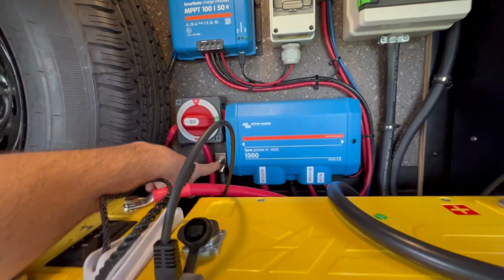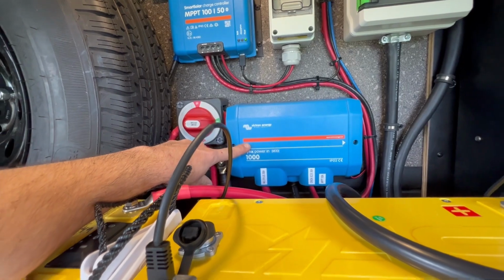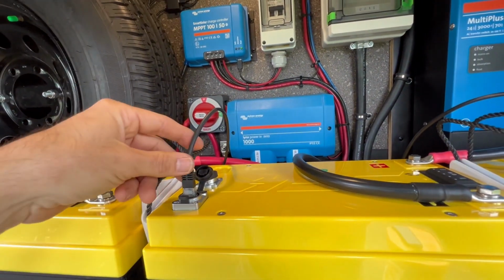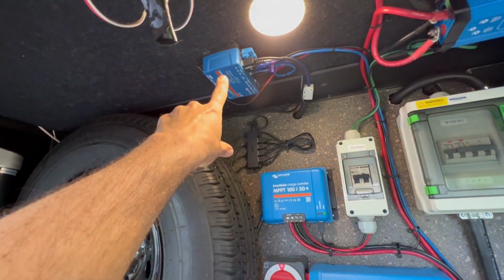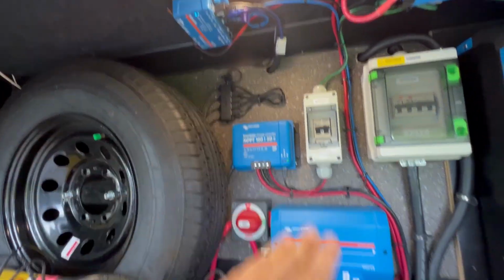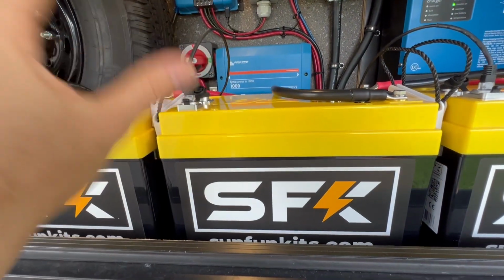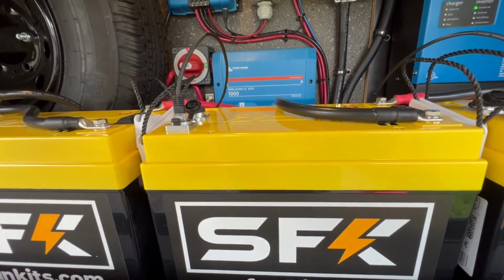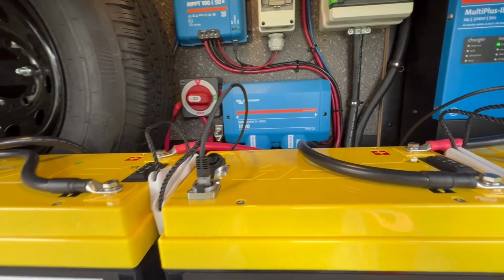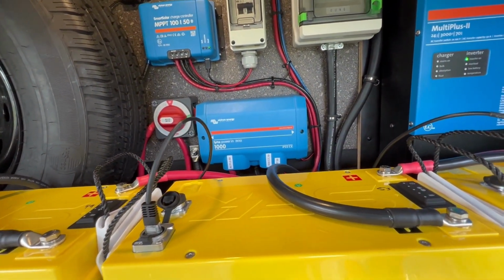The negatives go right to the terminal on this modified Lynx power in, and that's because each battery is sending data to the Cerbo, and the Cerbo is communicating with these SFK batteries via a dedicated SFK driver, which we download onto the Venus operating system. I'll show you that when we get to it.